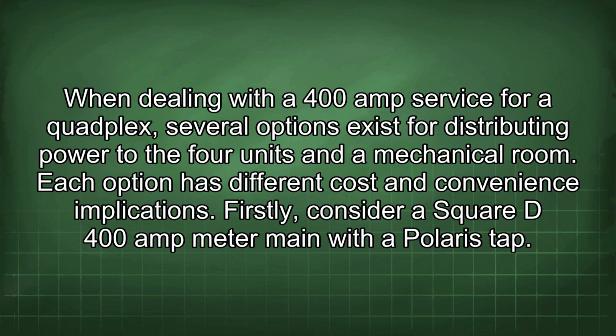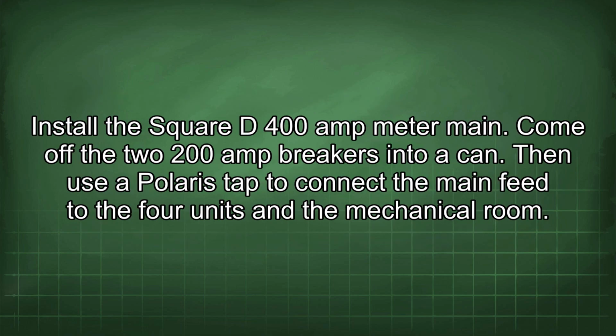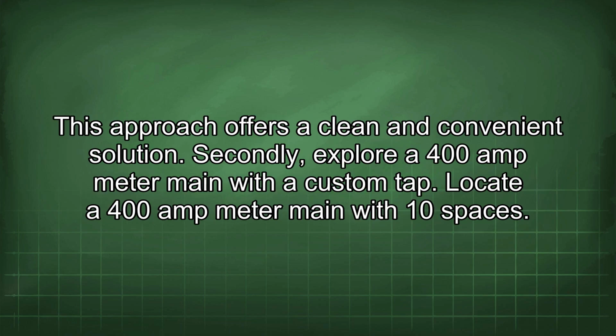Firstly, consider a Square D 400 amp meter main with a Polaris tap. Install the Square D 400 amp meter main. Come off the two 200 amp breakers into a can. Then use a Polaris tap to connect the main feed to the 4 units and the mechanical room. This approach offers a clean and convenient solution.